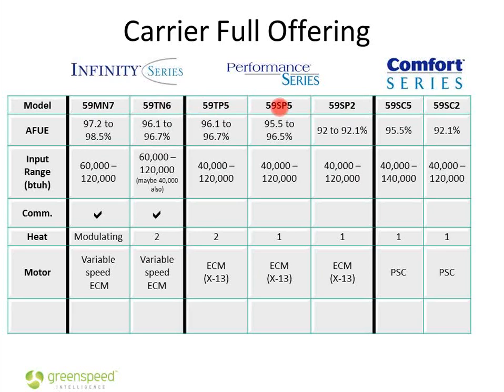Matt asks what PSC stands for. PSC is permanent split capacitor. It is your basic residential non-efficient blower motor. ECM is electrically commutated motor, and that comes in 2 flavors. There's what we call the X13 version, and there's a full 2-way variable speed one.